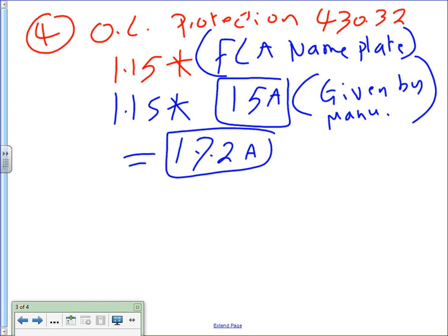What does the overload do, guys? It protects the motor from being overloaded. So if you are supposed to pump, as I always say, water to two stories, and you install it to pump it to six stories, now you're overloading your pump. Cool? 17. The last thing is number 5.